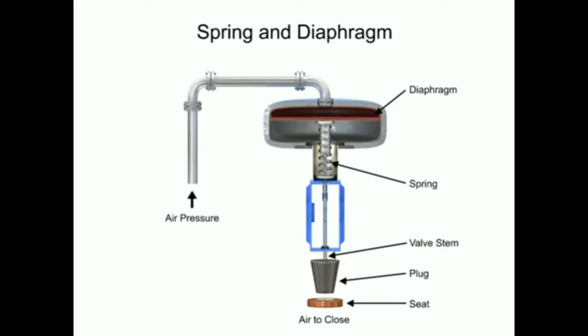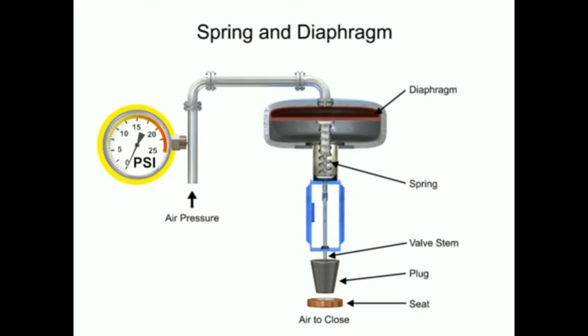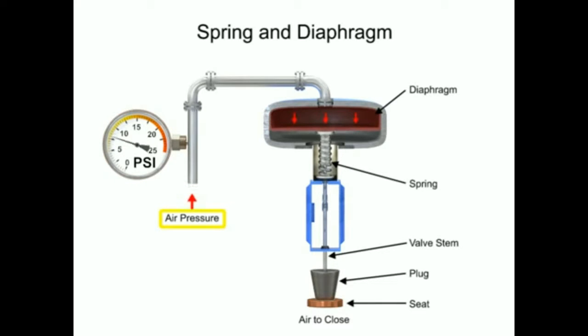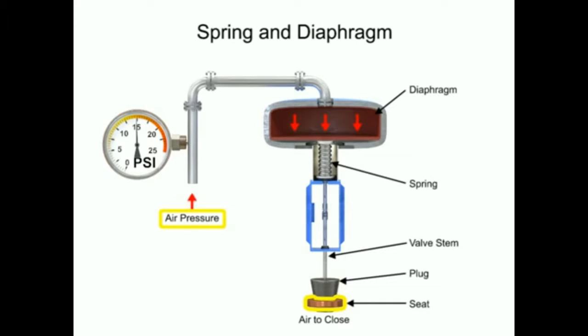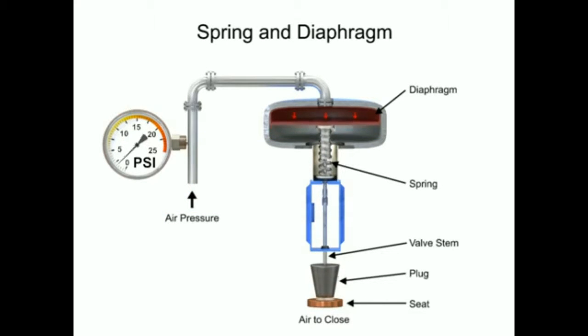As the name suggests, the spring and diaphragm actuator uses a spring and a diaphragm to move the valve stem and plug. A 15 PSI pneumatic signal enters the housing at the top of the actuator. As pressure is exerted on the diaphragm, a downward force is applied against the spring which moves the restrictor. The diaphragm moves until it creates an equal but opposing force against the spring, at which time the motion stops as the plug meets the valve seat. With no air pressure, the restrictor is pushed upward by the spring to act as a normally open control valve.